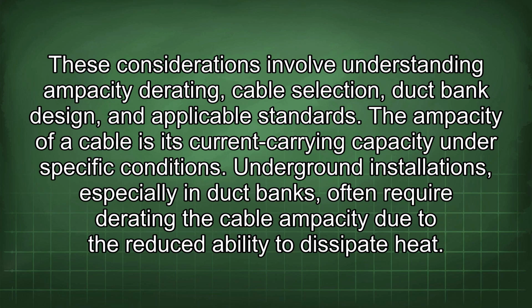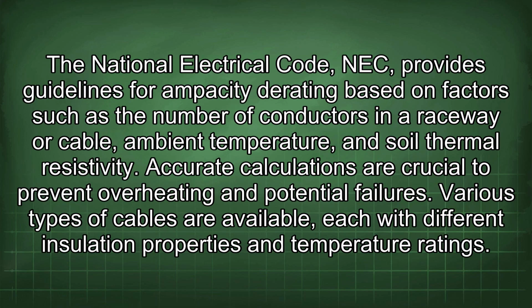The ampacity of a cable is its current carrying capacity under specific conditions. Underground installations, especially in duct banks, often require derating the cable ampacity due to the reduced ability to dissipate heat. The National Electrical Code (NEC) provides guidelines for ampacity derating based on factors such as the number of conductors in a raceway or cable, ambient temperature, and soil thermal resistivity. Accurate calculations are crucial to prevent overheating and potential failures.